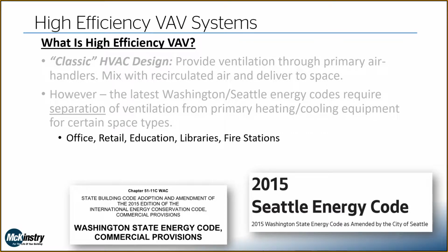So this is only for certain space types, though, which the code lists as office, retail, education, libraries, and fire stations. And it should be noted that this is referring to space types and not building types. So if we're talking about an education facility, the gym, for example, does not necessarily need to meet this DOAS provision of needing to separate out the ventilation air, but the rest of the school would.